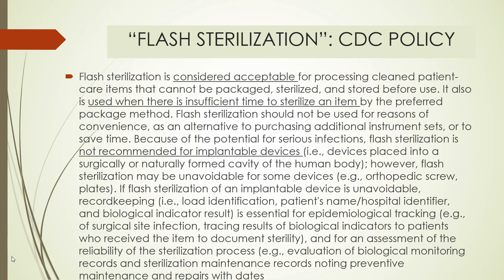And this is the reason that operating rooms and facilities have you sign a release agreeing to flash sterilization, so that you are accepting some degree of liability when you agree to allow flash sterilization, because you are increasing the risk to a patient. And here again, we have had lawsuits here in Missouri. Some of them have been rather significant, where patients have developed rather serious post-operative infections that resulted in some significant damage, and somehow the plaintiff attorneys were able to find out that the instrumentation was flash sterilized. So if you have to do it, you have to do it, but keep in mind that flash sterilization is not a preferred means to sterilize anything.